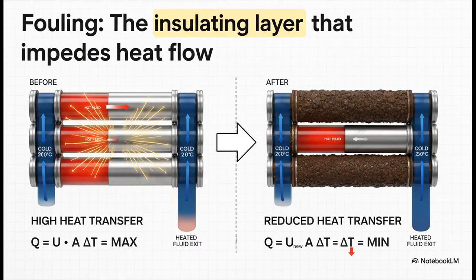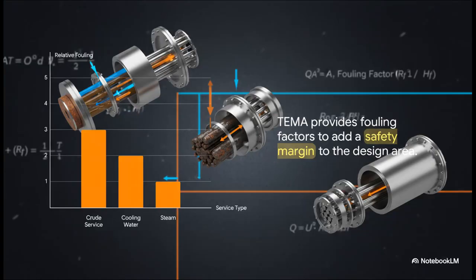Fouling is pretty much the arch nemesis of every single heat exchanger out there. It's just the buildup of junk, scales, sludge, whatever, that forms this insulating blanket right on the tube surface. And that layer directly fights the flow of heat, which means your exchanger's performance is just going to get worse and worse over time. Now, to fight back against this inevitable drop in performance, engineers design in a safety margin. TEMA actually provides standard fouling factors that we build right into our calculations. So for a really clean service like steam, that factor is tiny. But for a really dirty service like refinery crude, we have to add a significant amount of extra surface area just to make sure the exchanger can still do its job months down the line when it's all fouled up.